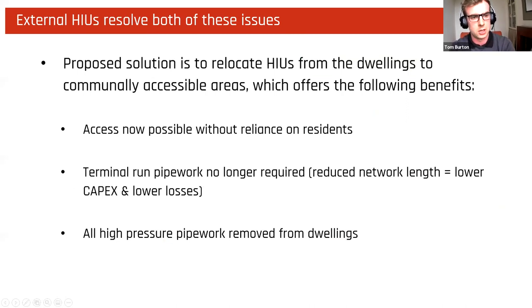Great, thanks. So external HIUs are a very easy solution to both of these issues. What we mean by external HIUs is moving the HIUs from the utility cupboards in the dwellings and putting them in areas where they're accessible from communal areas, such as the corridors in a flat, so you'd have an extra door in the corridor which you'd open, with the HIUs in there. The best way to optimize the design to minimize the extra floor space required is to put two HIUs per floor, per cupboard. You can also then set up multiple risers, with the risers actually running up through these HOU cupboards.